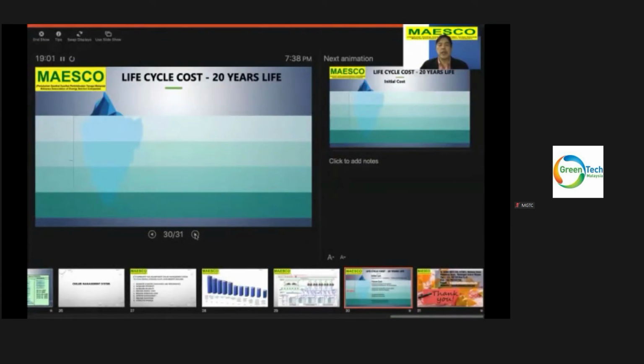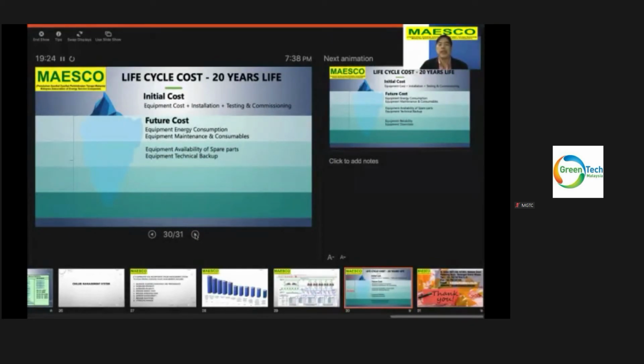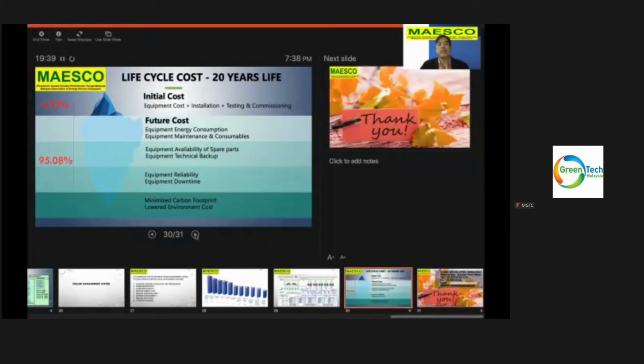Last but not least, always look at the life cycle cost. Bear in mind the chiller is a 20-year chiller, and do not buy based on initial costs, which include equipment costs, installation, testing, commissioning. All these costs only represent a small percentage. You must always look at the future costs: equipment energy consumption, equipment maintenance, availability of spare parts, technical backup, equipment reliability and downtime, minimizing carbon footprint, and lower environment costs. Now, initial cost is only 4.92%, whereas 95.08% is there. If you choose the wrong chiller, you have to bear with the 95.08% cost for the next 20 years. So let's be smart and reduce the carbon footprint by selecting the right chiller.